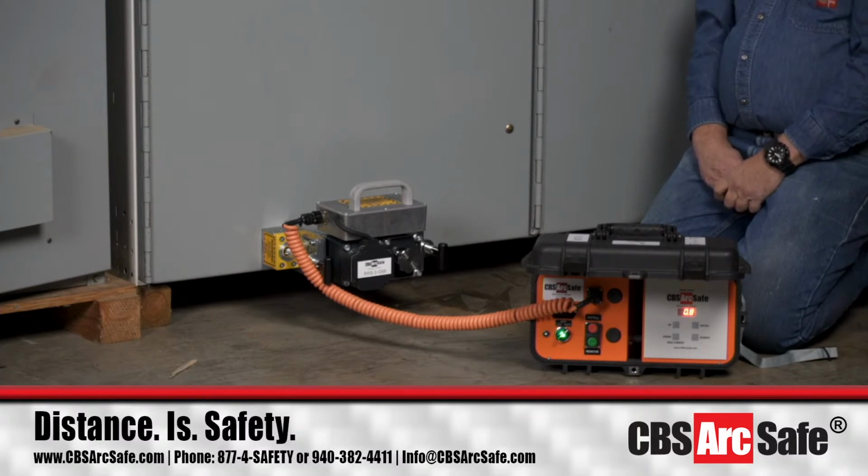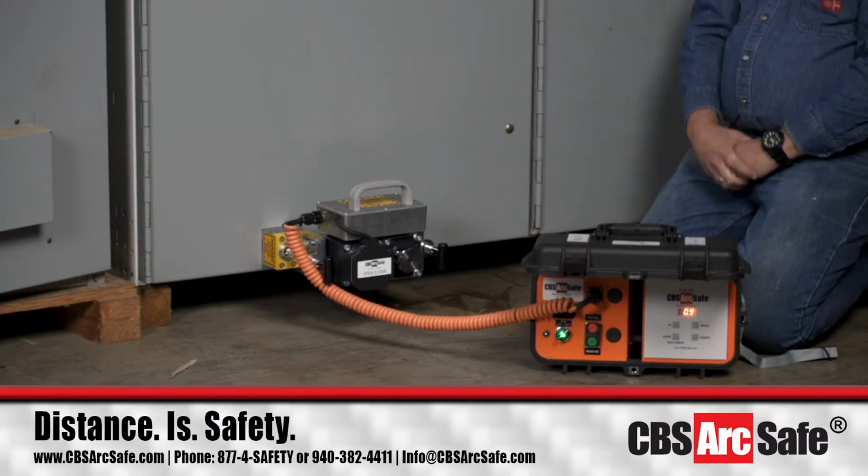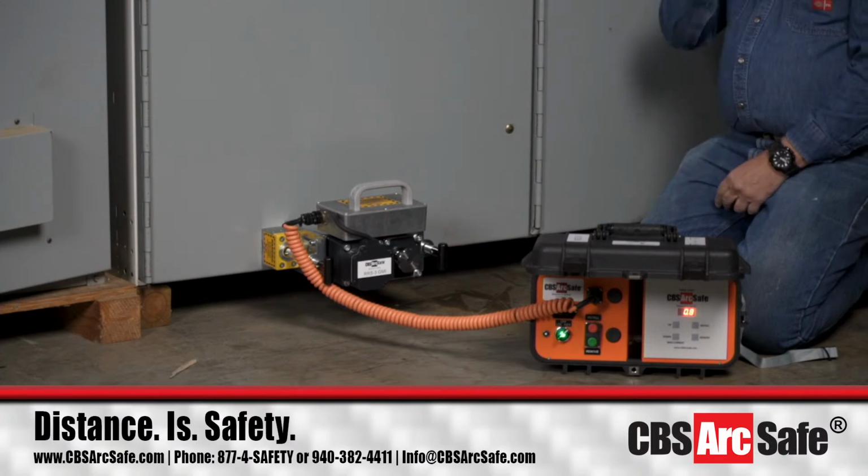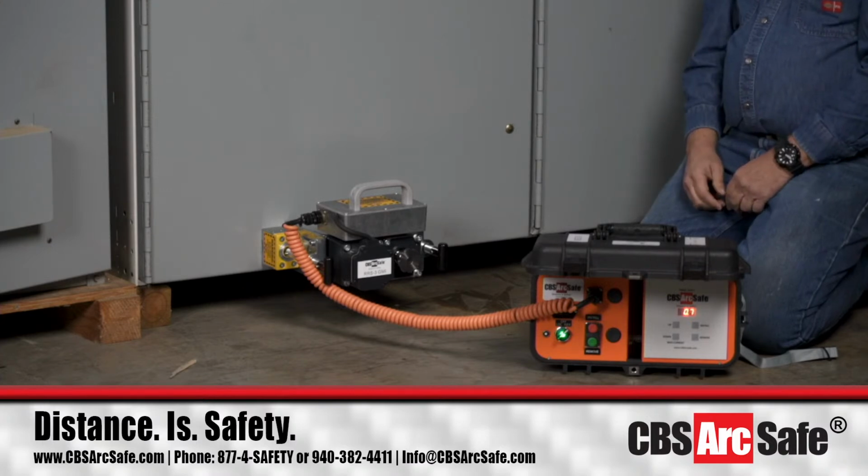Some of the funny things that you find out when you get in this business, you realize that circuit breakers are meant to be racked at the rate a human being does it. Trying to go much faster can actually damage switchgear. So we use the motor speeds based upon human experiments with people like me going up to our Gainesville warehouse and somebody timing me on racking a circuit breaker in and racking a circuit breaker out.